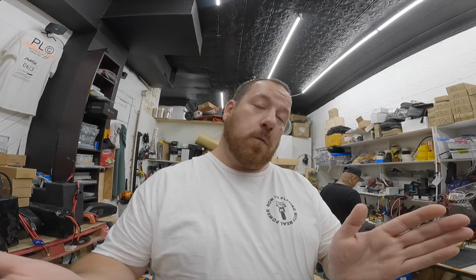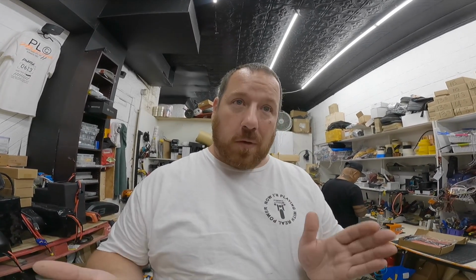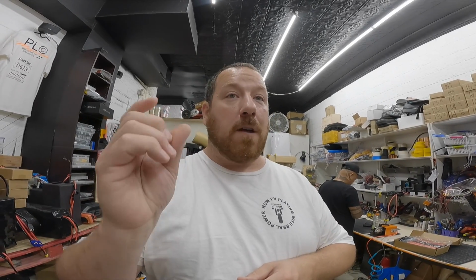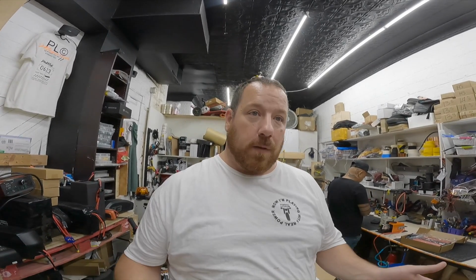If a controller says 500 amps maximum current, and you have 25% field weakening, that means you're gonna pull an extra 125 amps. So it's not 500 anymore, it's gonna be 625 with 25% field weakening.